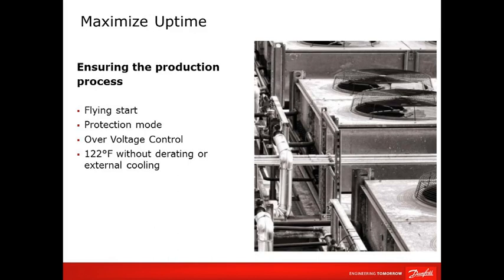Obviously, maximum uptime. Again, this is just a reminder: we're protecting not only the motor and the process equipment, but also trying to enhance the life of the drive. We can install the drives in some pretty extreme applications, for example 122 degrees F. So we do have some flexibility, and again, without having to derate, which means you have to oversize the VFD for the application. In Danfoss's case, if it falls under that temperature, there's no requirement for that.